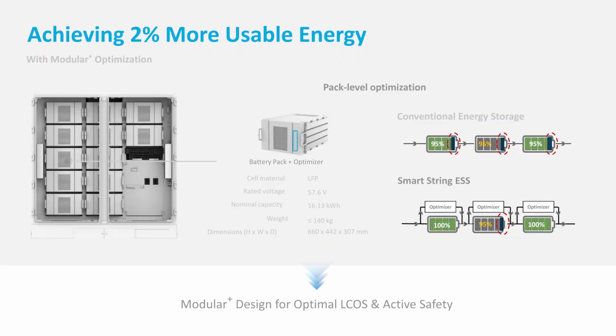Okay. This is a snapshot of our ESS just to talk about achieving 2% more usable energy. Because we have pack level optimization on our battery storage system, we can make sure that each battery has its own battery management system that makes sure it has its own state of charge done every day. So it calibrates the battery every day so that you can have the full usage of the battery. In traditional systems, you have to manually do SOC calibration, which is only done maybe twice a year or once a year. So if one battery is at 95% and the other batteries are at 100% connected in series, you can only draw 95% out. Okay, because they are mismatched in the battery cells itself.